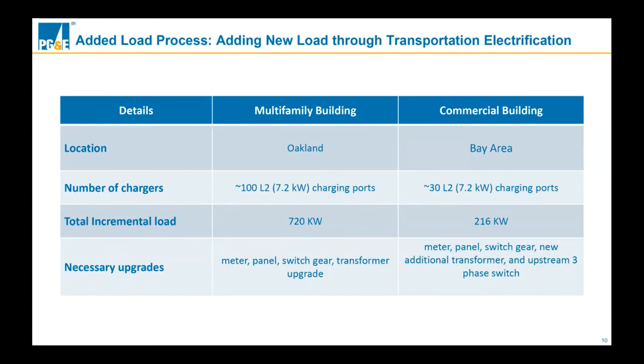On the far right, in the next column, you have a commercial building—I think this one might be a workplace somewhere in the Bay Area. They installed around 30 Level 2 charging ports or so, for an incremental load of 216 kW, and required a meter panel, switchgear, and an additional transformer. This is an example where an upstream upgrade was required, so they had to switch out a three-phase switch.